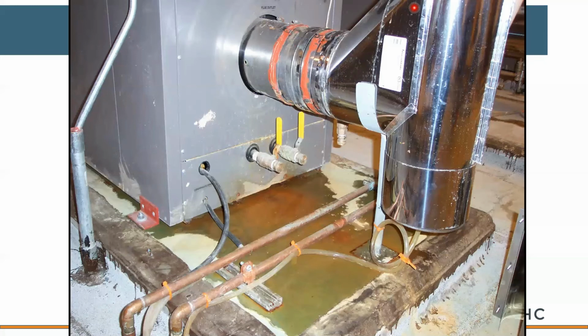Facility guys got a little nervous, so they called the contractor back in. He reads the O&M and says, "Oh, I can't use this vent material. I have to use a high grade of stainless steel." So he redid the venting and added a boot tee here to allow all that moisture to get out of the system. Unfortunately, while it was condensing in the flue products, it was also being allowed to rush back into the boiler. This particular boiler has an epoxy lined heat exchanger, and it doesn't do well with acid. You can see that it has failed in less than a year.